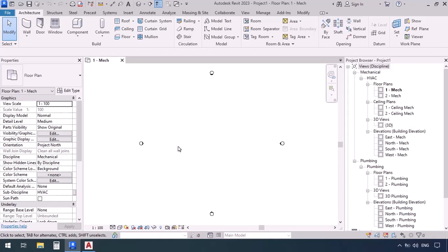Now how can we show these system types in Revit, and why should we clarify them there? We have two reasons. First, depending on the system type of a duct, we can graphically adjust it — we differentiate the colors of exhaust, supply, and return ducts so that looking at a plan we can see different colors for each type. Second, if we are adjusting our design or sizing in Revit, each duct type has its own special properties — air velocity and pressure drop are different in each.